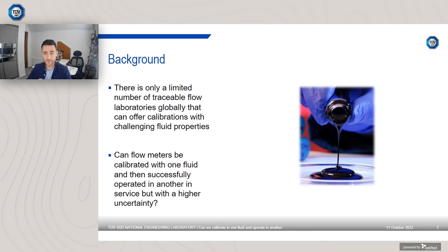Another fluid that's of interest is high viscosity fluids. So I've got here a heavy oil. Here at NEL we have a high viscosity flow facility that goes up to 2000 centipoise. We've completed a fair amount of work regarding low viscosity and high viscosity calibrations and how the effect of viscosity on common flow meters.